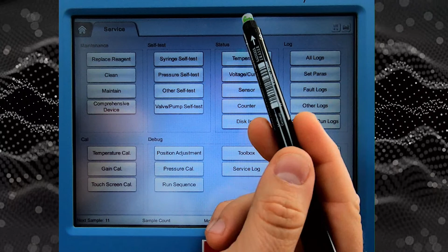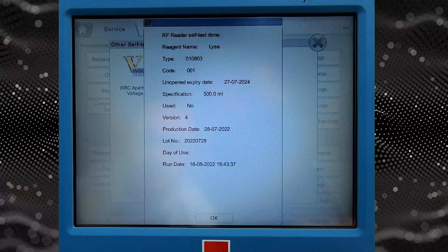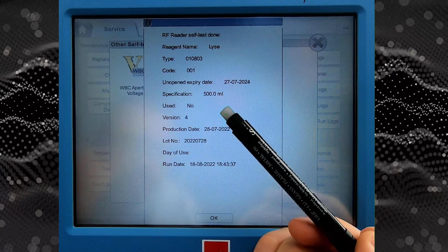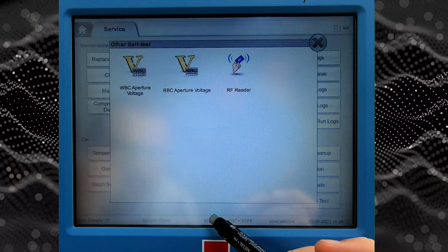This will be better for the reagent. And here we have some syringe self-test, as you can see, pressure, other self-tests. What can be useful is the RFID reader test. So it's actually not a test for the reader, it's testing the cards. And right now I use the same card, and as you can see, this is the card for lysis type, expiration. It was not used before, so it's a new one. Production date, all those things. So this can be used to test if the reader is working and if the card is valid or not, just in case.